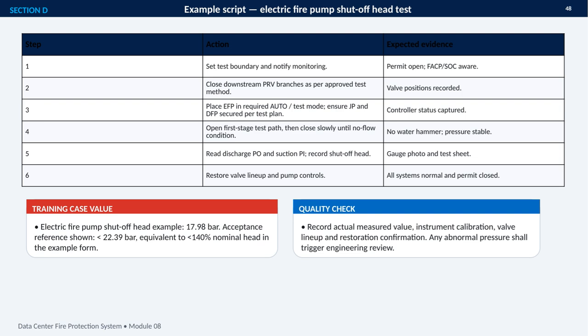The first stage test path is opened, then closed slowly to reach a no-flow condition without water hammer. At that point, the discharge and suction readings are captured, with a gauge photo and completed test sheet. The example shutoff head is 17.98 bar, compared with an acceptance reference below 22.39 bar. Finally, the valve lineup and pump controls are restored. All systems are confirmed normal, and the permit is closed.